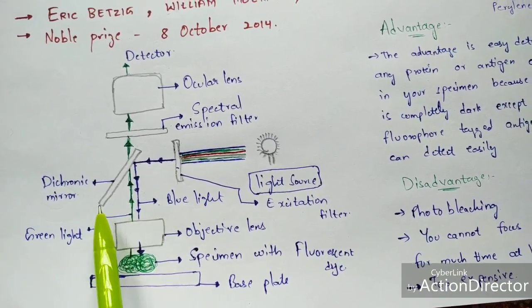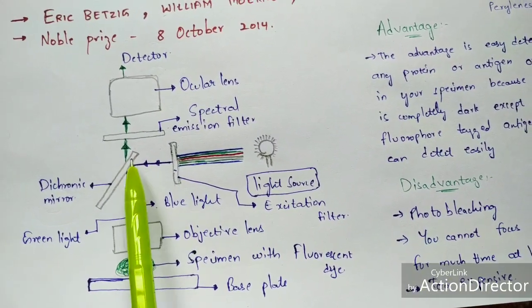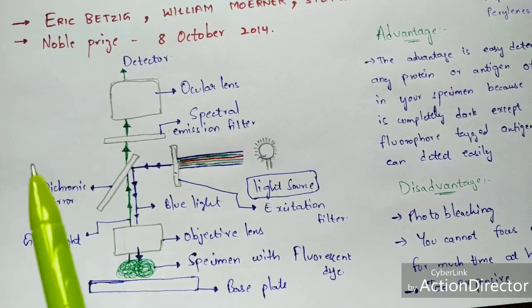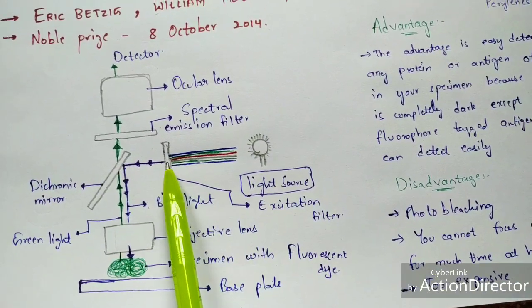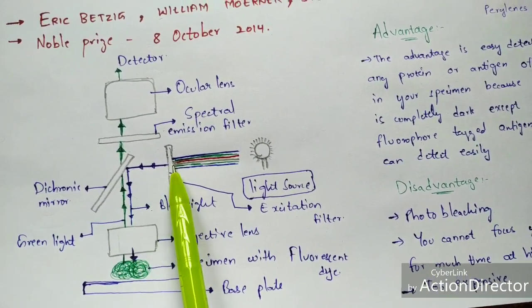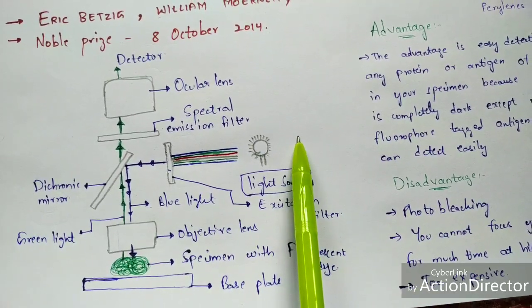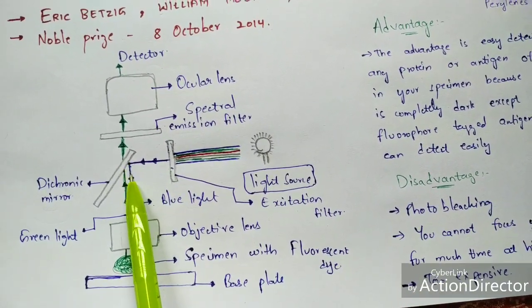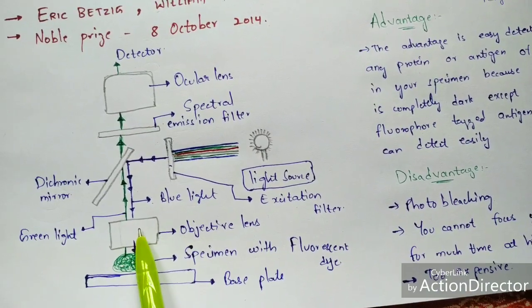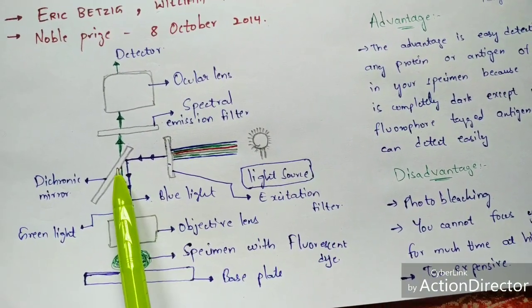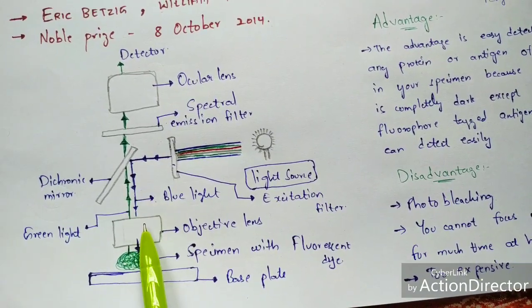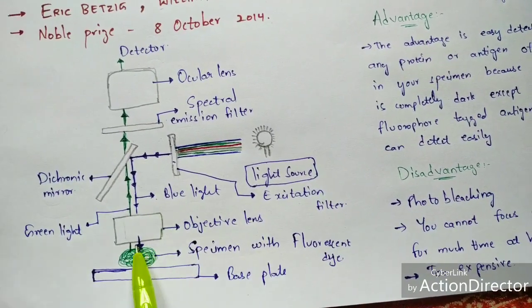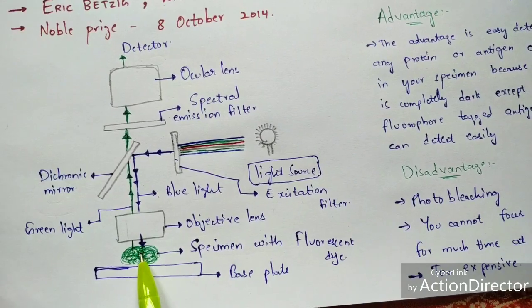The dichroic mirror plays a major role because it exhibits two properties: it reflects the light, and it also sends light to the image detector. The dichroic mirror reflects the blue color light and directs it to pass upon the objective lens.